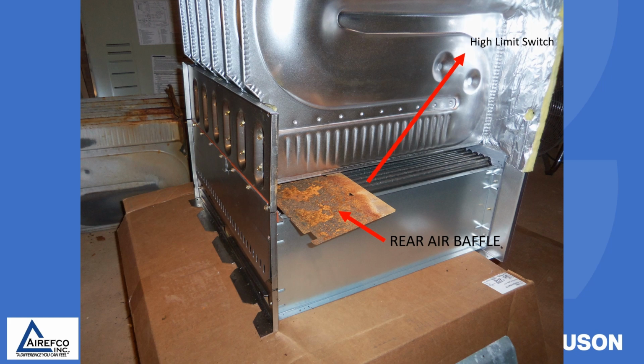So if you don't have a parts list or a breakdown to show you this rear air baffle is necessary for that particular furnace, many technicians replace the primary and secondary heat exchangers without putting the rear air baffle in, and they immediately have high limit switch trips because that rear air baffle is not there to direct the air towards the front of the furnace.